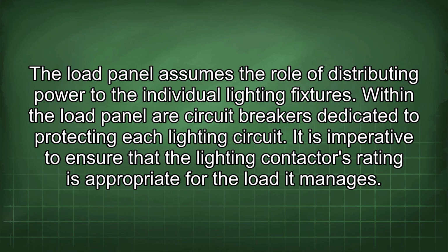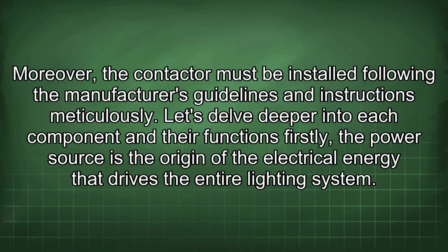The load panel assumes the role of distributing power to the individual lighting fixtures. Within the load panel are circuit breakers dedicated to protecting each lighting circuit. It is imperative to ensure that the lighting contactor's rating is appropriate for the load it manages. Moreover, the contactor must be installed following the manufacturer's guidelines and instructions meticulously. Let's delve deeper into each component and their functions.